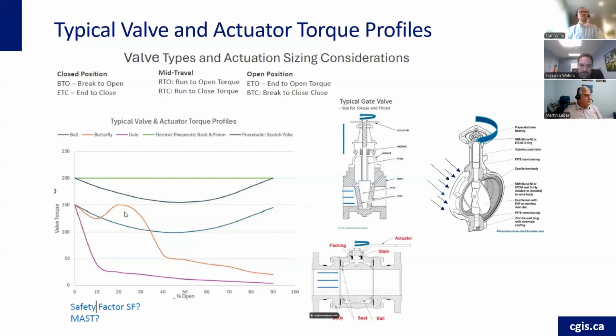We'll look at the butterfly valve, the orange one here. If that butterfly valve opens, it drops off after a certain percentage, around 20 to 30%, or around 20%. You'll see a blip in the torque, because that's called the dynamic torque, when the fluid is flowing around the disc and there's a resistance to opening. Once you get past that point, it drops off quite quickly, similar to the gate valve. Certainly when you go to close it, you're going to have the same sort of profile that you have when you're opening it.